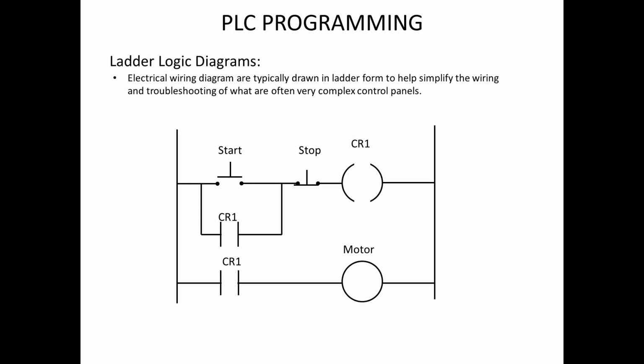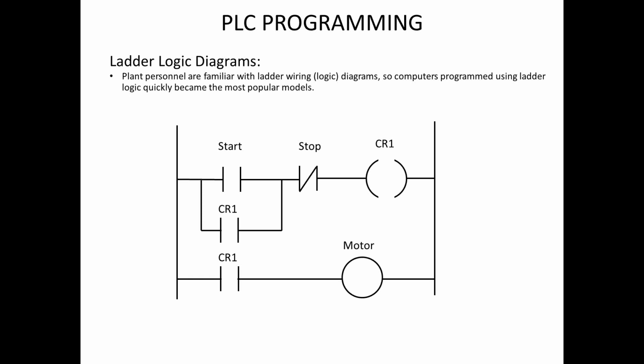And when that CR1 is energized, the CR1 below that as well is energized, and you get that motor to actually run. So pressing that start push button starts the motor, and when you let go, the motor continues to run. As soon as you press that stop push button, that cuts all the power to that CR1 coil at the top, and that de-energizes it. That causes those contacts to open, and the motor stops. And so that was a wiring diagram. They did the same thing.